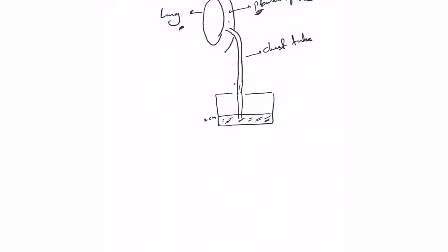It's exactly like if you have a cup of water and a straw in it. Try to blow in, you will create bubbles, but try to suck the air back. No, you only suck liquids, right? And this is the same thing. This is a safety mechanism where air will flow in, get into the water, and go out this way, but will never go back into the chest. So that's the first problem we kind of solved, right?